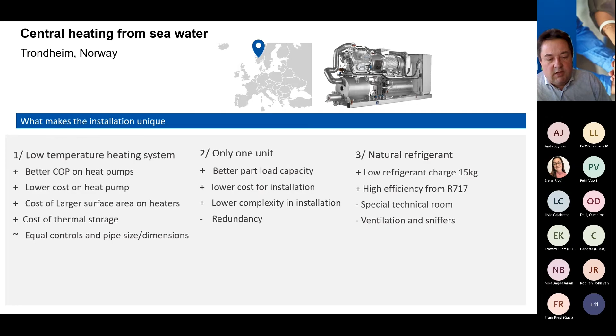So the application here is delivering a COP, or an efficiency, of 4.3. When it moves upwards in temperature, meaning the harbor gets warmer, like 5 degrees, it actually achieves a COP increase of 14%. It's calculated with a lift of 10 degrees, from 40 to 50.